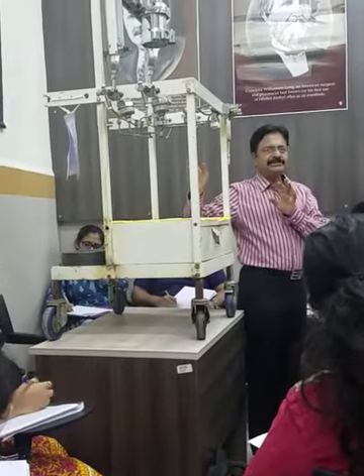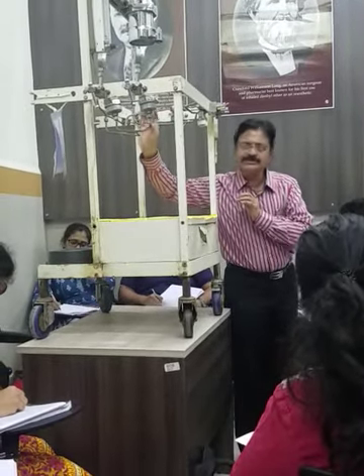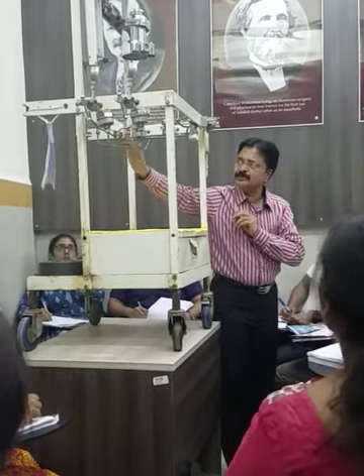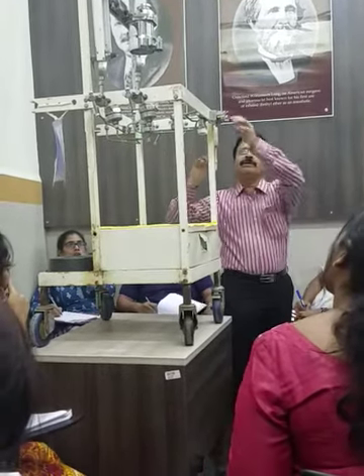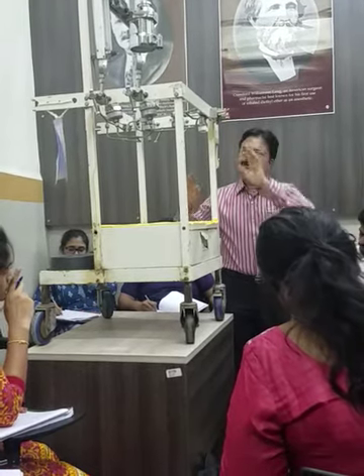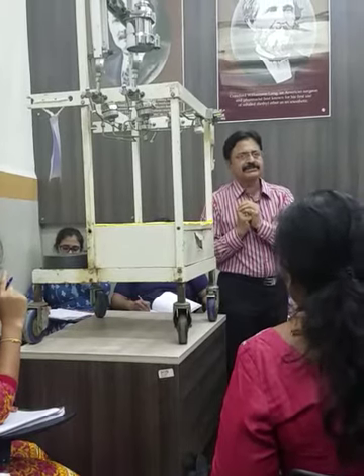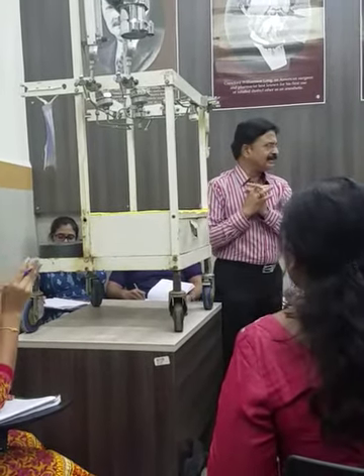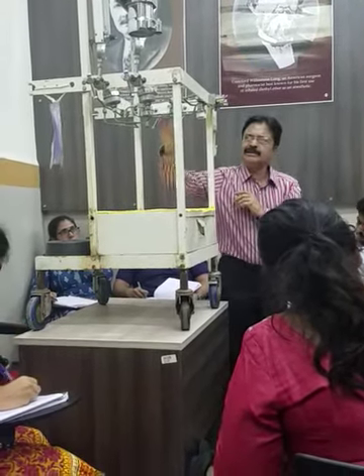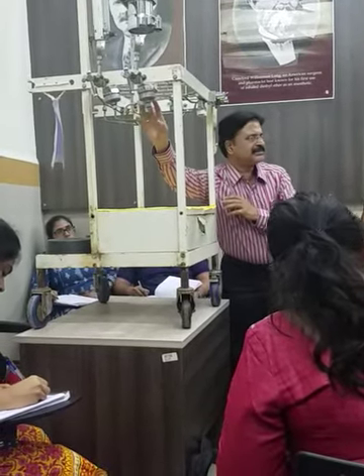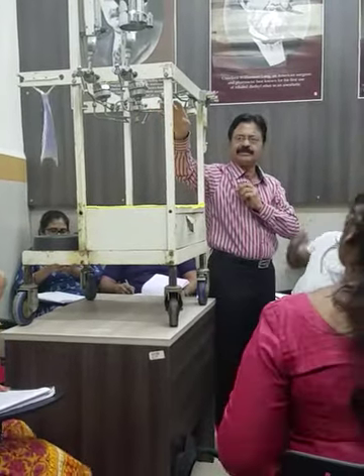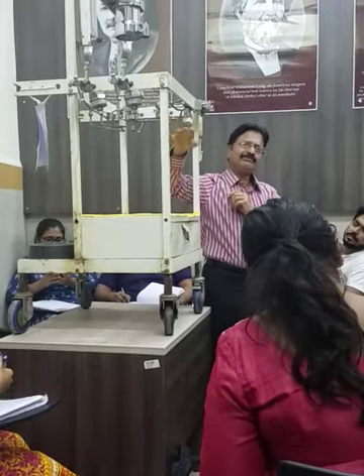The intermediate pressure system mainly consists of alarm systems — the oxygen failure alarm systems are one of the things. The oxygen flush is another part of the intermediate pressure system. In modern machines, you also have the oxygen fail-safe device. In older machines, the master and slave pressure regulators used to work as the oxygen fail-safe system. Now we have a separate fail-safe system in the intermediate system.